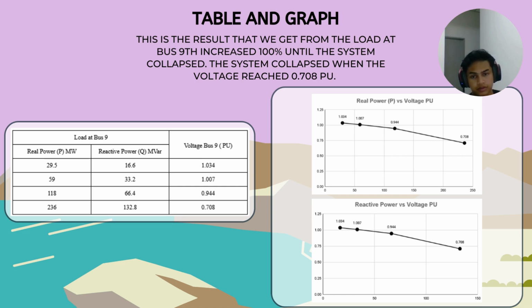The next one is 59 megawatt and 33.2 megavar, and the voltage we get is 1.007. Then the next one is 118 megawatt and 66.4 megavar, and the voltage we get is 0.944. Lastly is 236 megawatt and 132.8 megavar, and the voltage is 0.708.